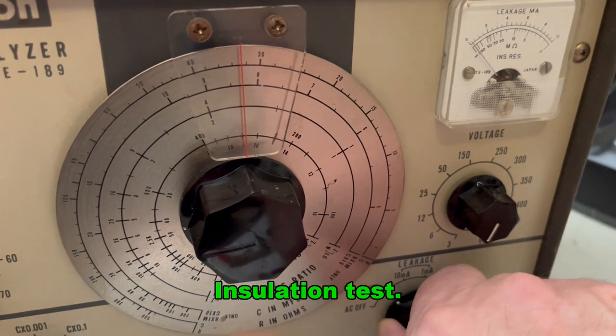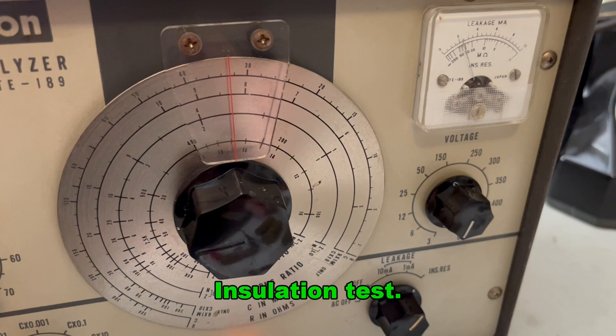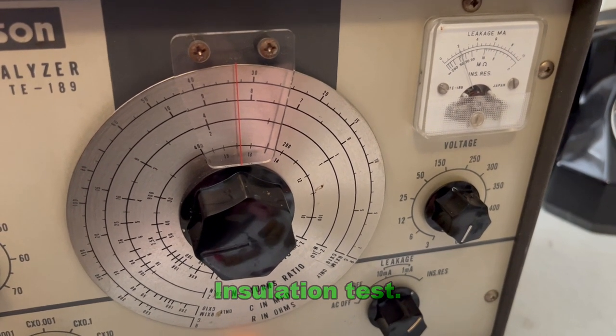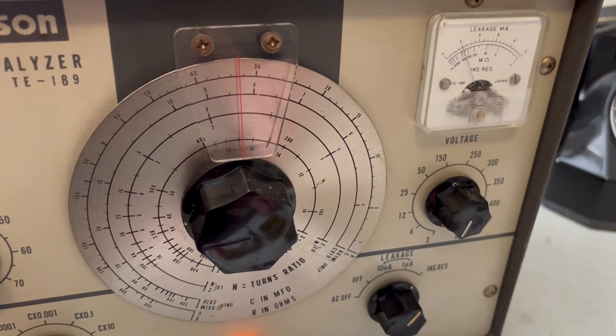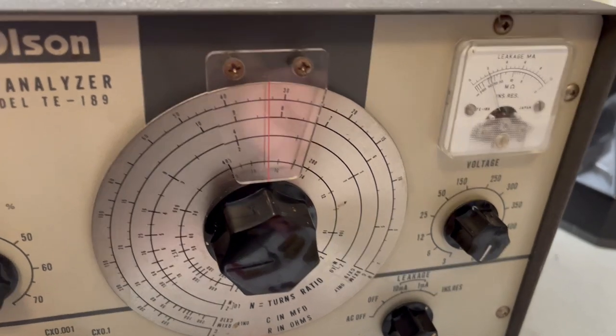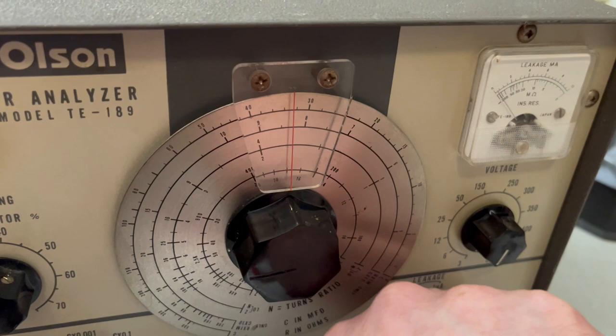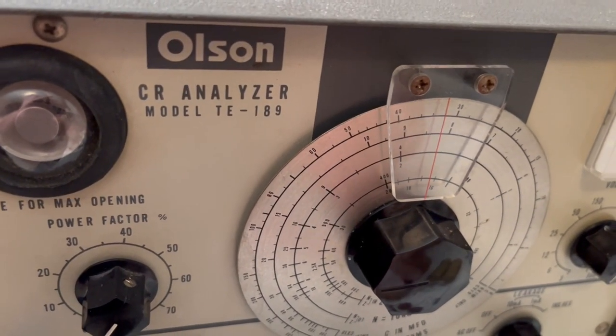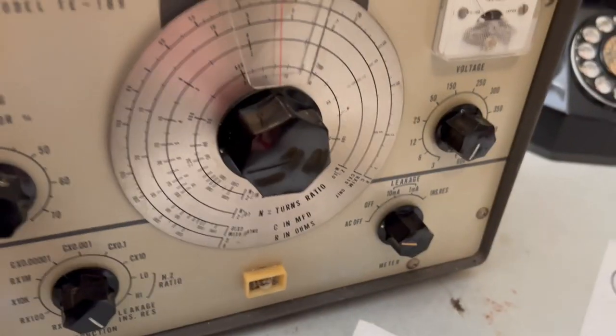Like I say, this one tested okay. Yeah, it's got a little leakage. It didn't come right back, and yeah, that would cause a performance issue of some sort, I think. So that one has some leakage associated with it, even though it measures out right.